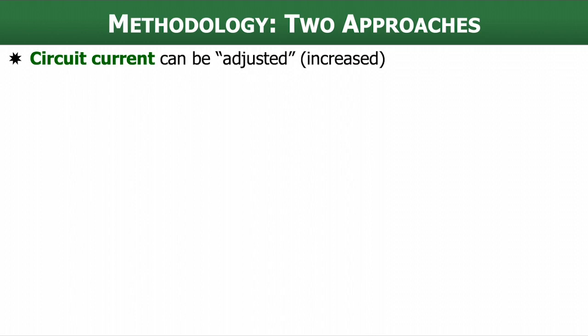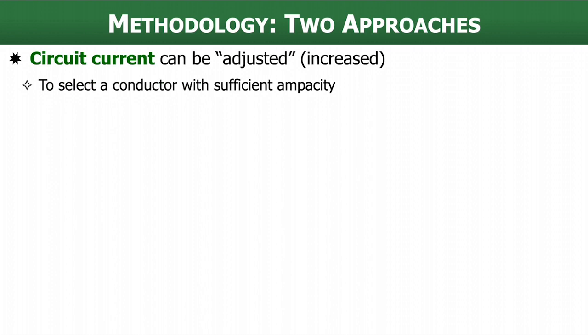So what about our methodology? There are really two approaches to determining what conductor is going to be right for a given circuit. The first is what I call adjusting the circuit current — we apply some factors to the circuit current through math to come up with a new adjusted circuit current. Then once we have that adjusted circuit current, we can pick a conductor that has the correct ampacity for it.